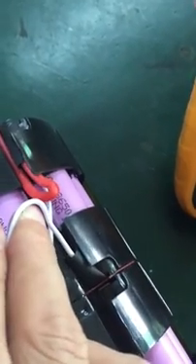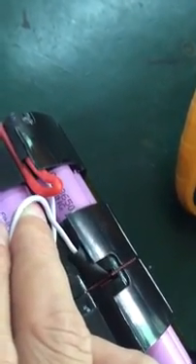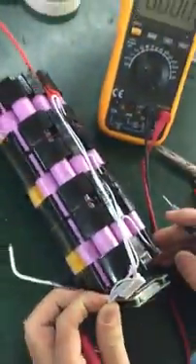Here, here. Always these wires are loose. So if you find that a voltage is not the same as the others, you need to check the voltage on this wire. Okay, thank you.